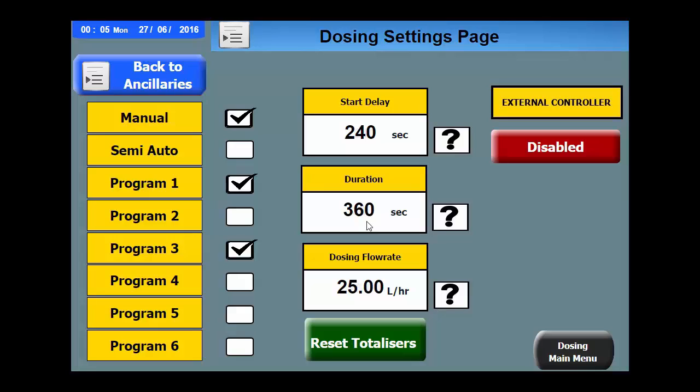Once dosing is complete, normal watering will continue until the next station starts and the cycle repeats. The dosing flow rate needs setting up during commissioning in order to properly account for the amount of fertiliser or wetting agent used. This is based on the setting of the positive displacement pump and can be changed here.